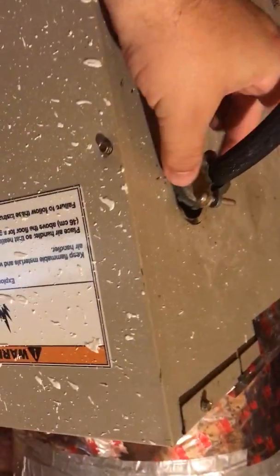It has pre-designed holes to be punched out for wire penetration, so you can wire it. The problem I see a lot is either no bushings at all, or the bushings have been pulled out. You can see this bushing was installed at one point. It would have been installed on the inside, screwed in, then the wiring fed into the top and clamped into that clamp. Now this bushing's pulled out, and you can see it's just open.